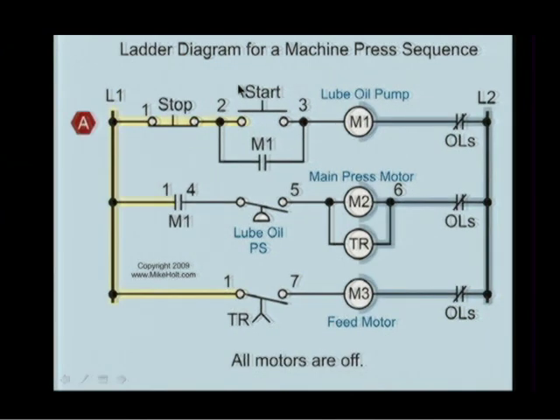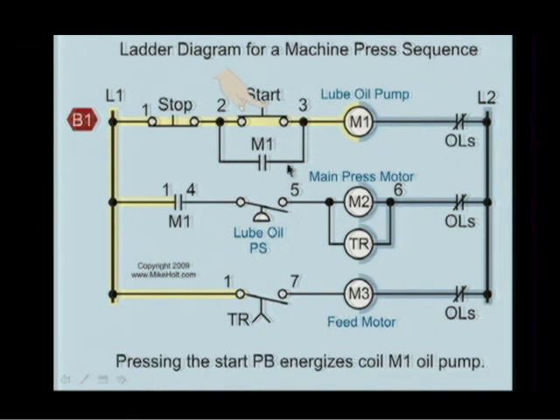All right. If I press the start button, we have voltage on line 2 taken care of. Here's a time relay contact. Here's a lube oil pressure switch. All right, let's press the start button. I press the start button, energize this coil, close the M1 contact that interlocks the motor. So the motor's now running. I now close permissive contact M1, which now permits motor 2, which is where the lube oil comes on. Motor 2 is permissive until the lube oil pressure indicates that there's sufficient pressure.